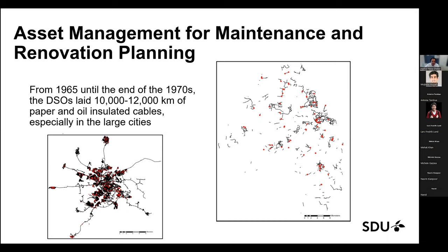and the DSO does not have the necessary budget to do that. So we can only replace around, I don't remember exactly, but I think it's around 20 kilometers every year. So that's not much, basically. So you need to prioritize, to have a list of underground 10 kV cables based on their fault vulnerability to know what to do. And here are district heating system pipes and thermographic faults that are observed. So the same thing we would like to do here, to know where to focus our maintenance efforts.